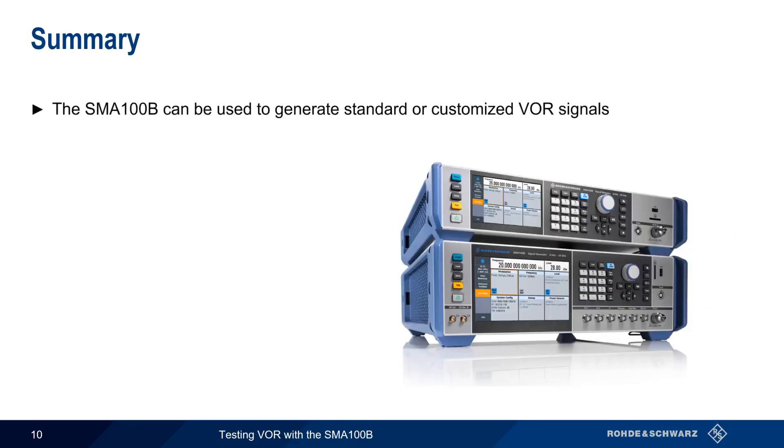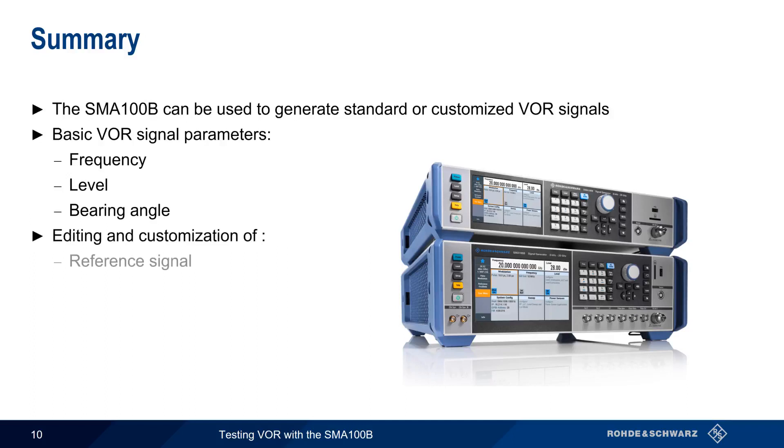In summary, the SMA100B can be used to generate standard or customized VOR signals. The three basic parameters in VOR signal generation are the frequency, level, and the bearing angle or radial. In addition, the various components of the VOR signal can be enabled or disabled or modified. These are the reference signal, the variable signal, and the COMID signal. This concludes our presentation, Testing VOR with the SMA100B.